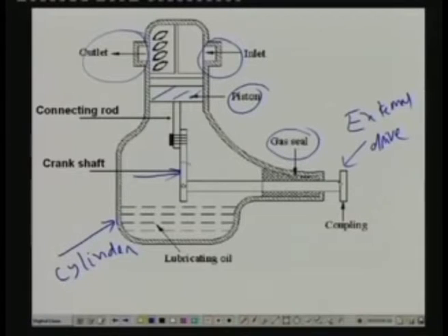One of the problems with this type of compressors, as you can see, is this shaft has to rotate. So, certain clearance must be provided at the seal so that it can rotate without too much friction. When you are providing a certain amount of gap here, there is a possibility of refrigerant leakage. So, this is one typical problem with the open type of compressors.